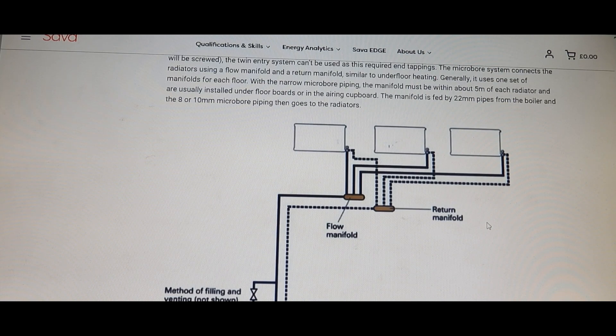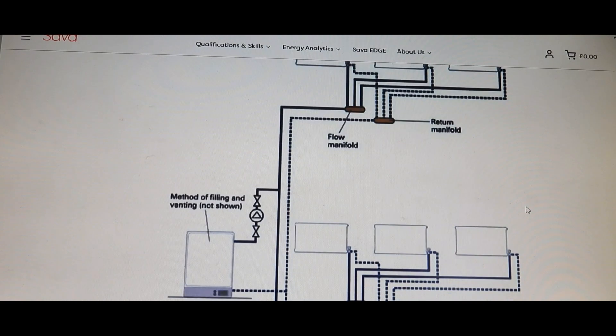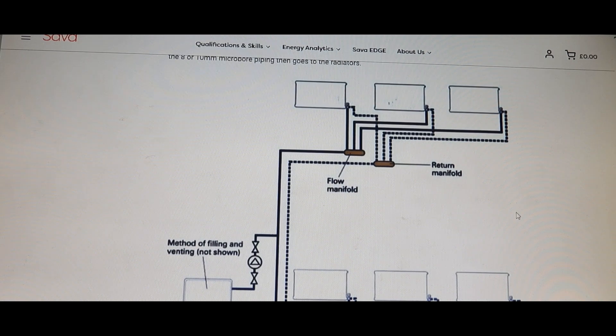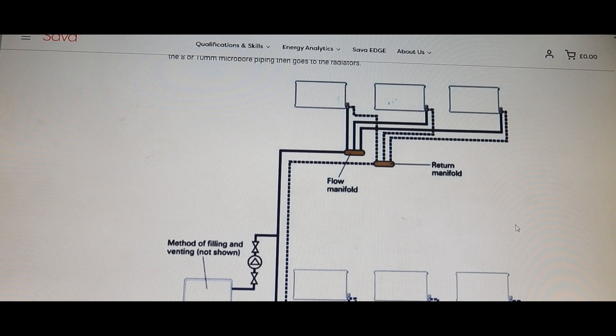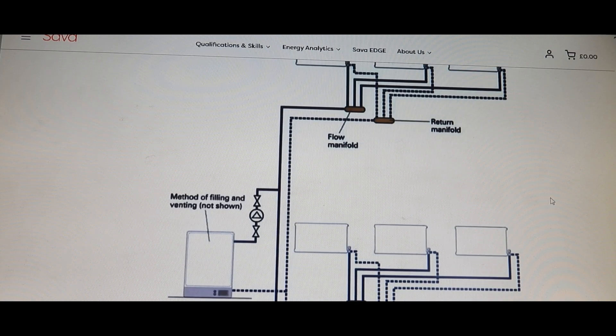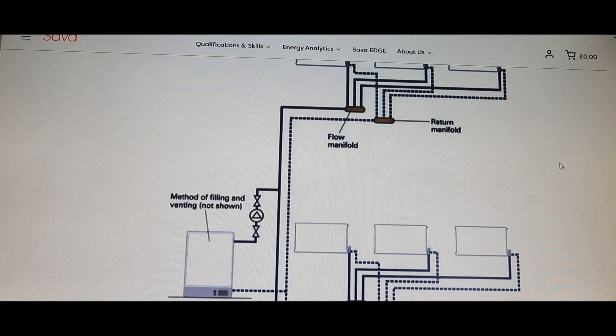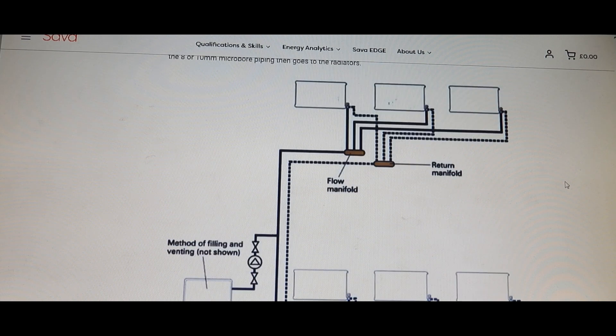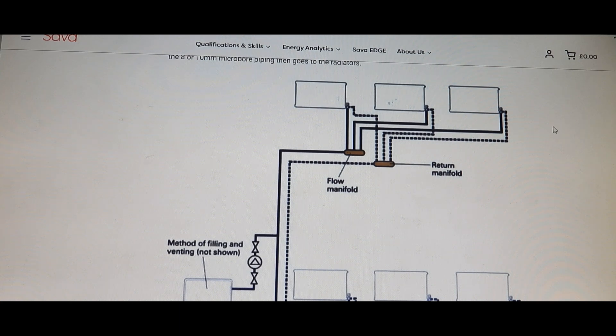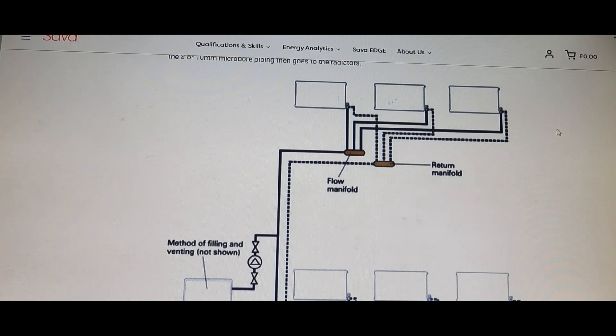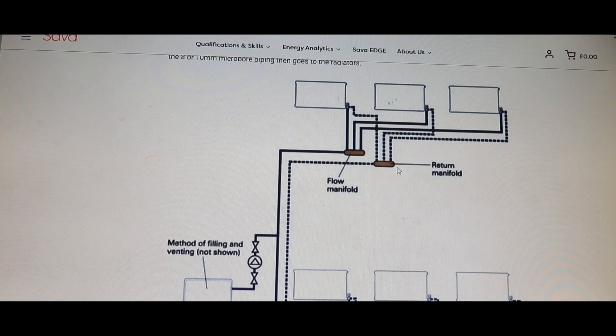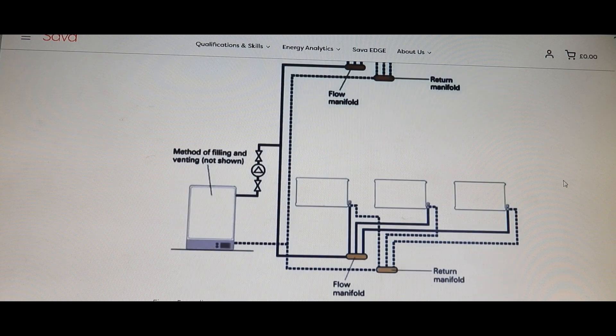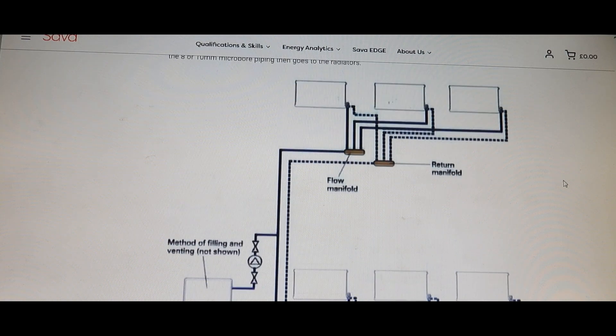Do remember it's 10mm, could be 8mm, the really thin stuff. It is efficient because it hasn't got much area to heat up from the boiler. It is not a bad system really, it's just it's got its limitations like everything else. So that's it with microbore. Be careful when you're thinking about just teeing off like from here or there and just running it to another room. You can do it, you can try, it may work, but I wouldn't suggest it. Best thing is to change the manifold for more ports.